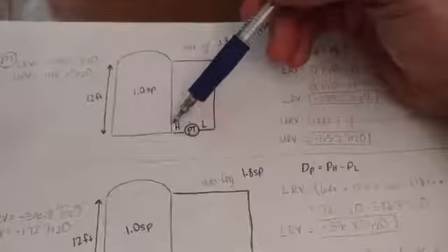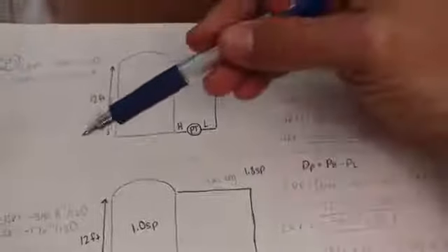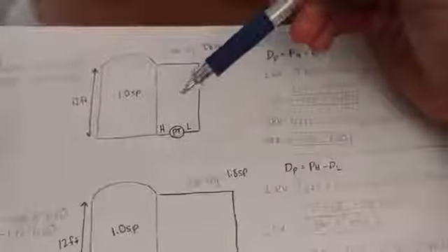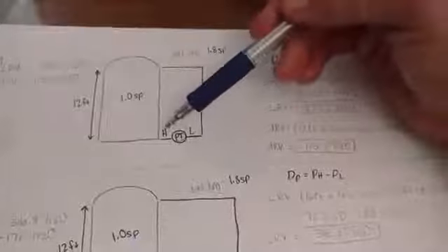So for our upper range value, we're going to look at this high side over here. We're going to look at the entire range because this is our upper range value. We're going to say 12 feet times 12 inches of water times our 1 as the specific gravity, because we're looking at this side now.